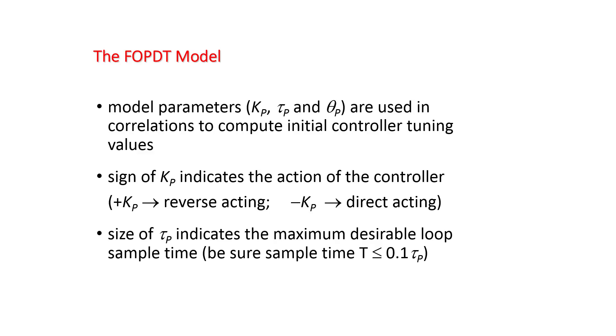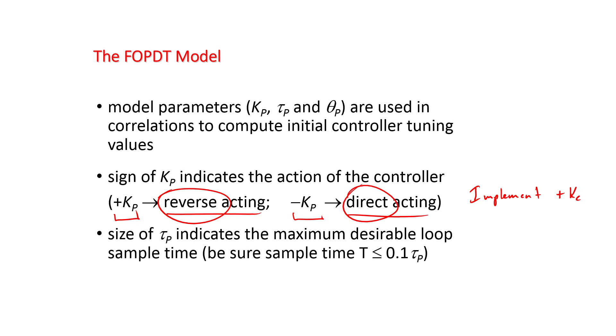We need to obtain k_p, tau_p, and theta_p to get the controller tuning values. Note that if k_p is positive, you have a reverse-acting controller; if k_p is negative, it's direct-acting. Most controller implementations always use a positive k_c, and then you set it to either direct or reverse acting based on the sign of k_p.